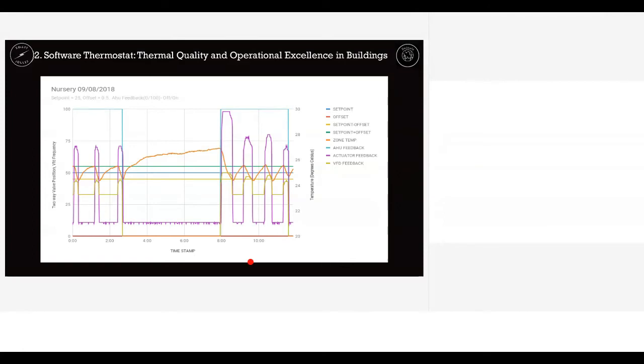This is a simple graph. There are many things to understand here, but let me explain. This violet spike that you see is the opening and closing of the two-way motorized valve that is controlling the chilled water flow. And then there is a blower fan. The blower fan is connected with a VFD, a variable frequency drive, and that VFD is this yellow line in between. So there are two controllables here, two things you can control: the amount of cold air going into the area, and the amount of chilled water flowing through the cooling coils, or the copper coils, in the heat exchanger.